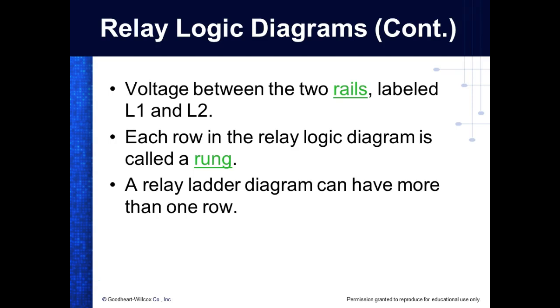Each row - and this isn't exactly true either - each circuit in the relay logic diagram is called a rung. I don't know exactly what the book says, but it starts with single element circuits, with no parallel devices. But we know we can hook outputs and inputs in parallel, and as soon as I do that, I'll have a different line. A relay logic diagram can have more than one rung.